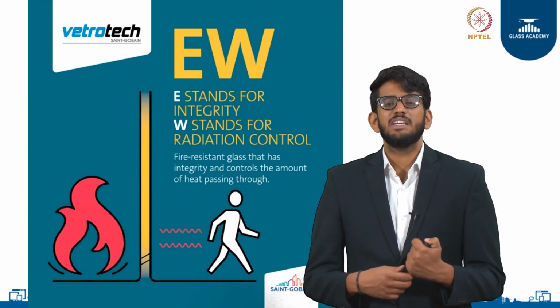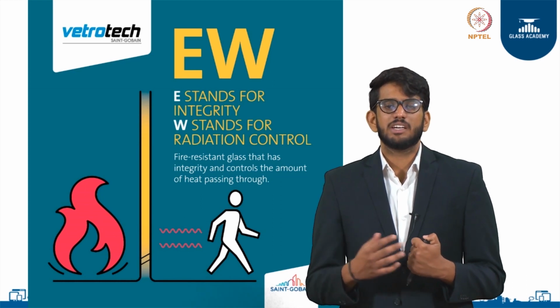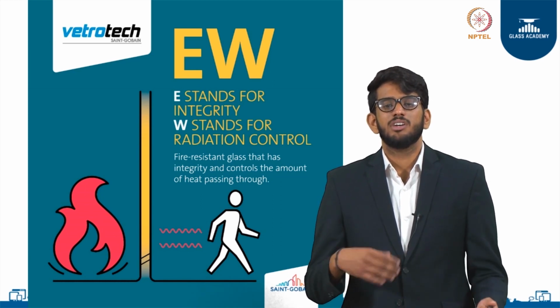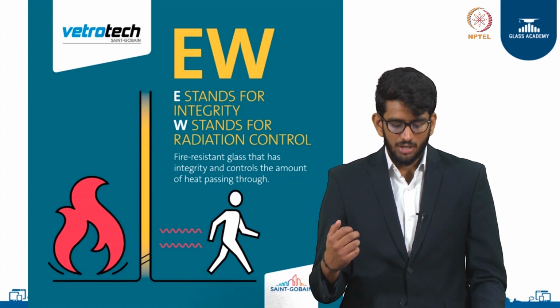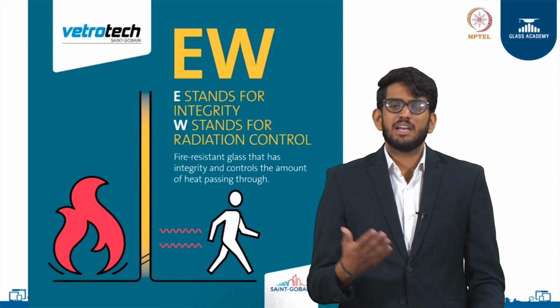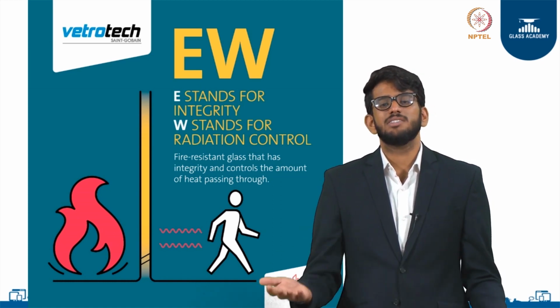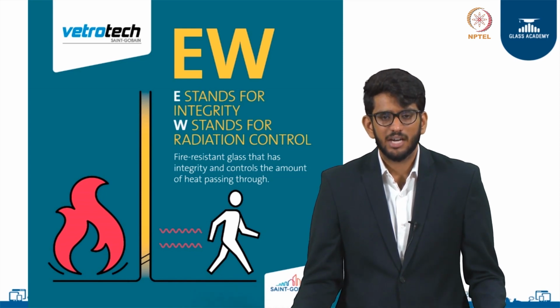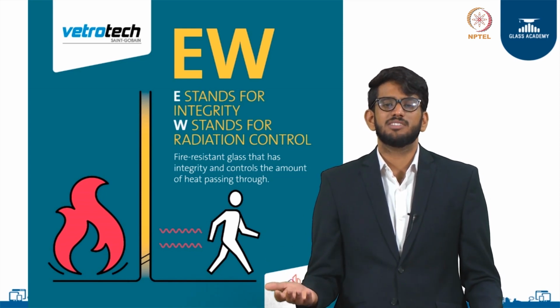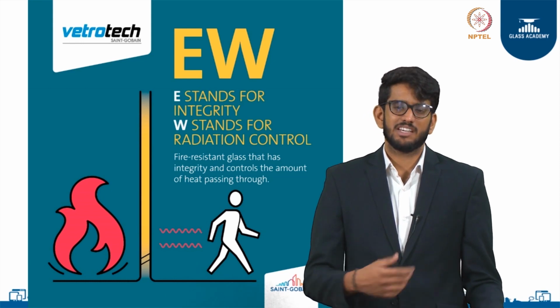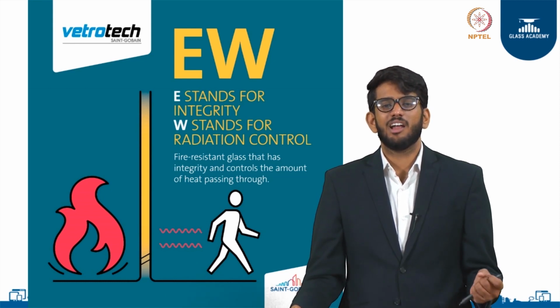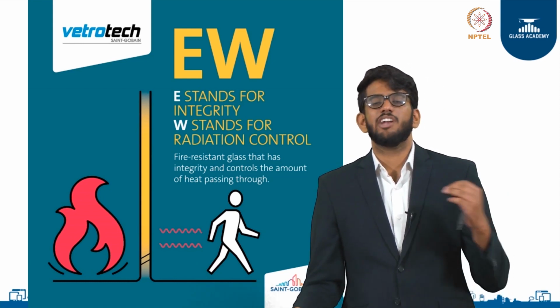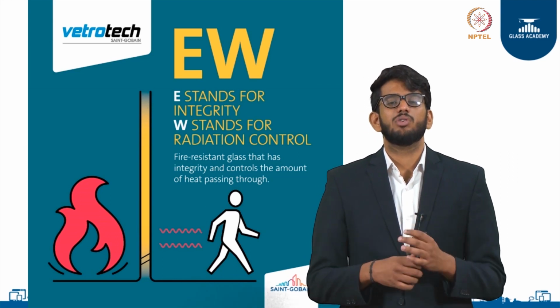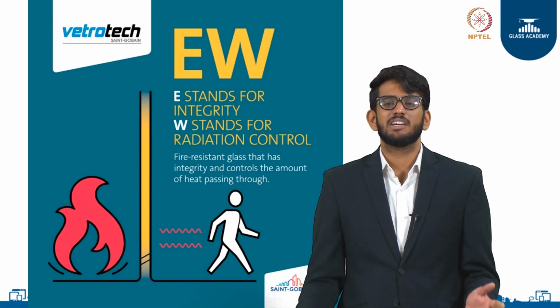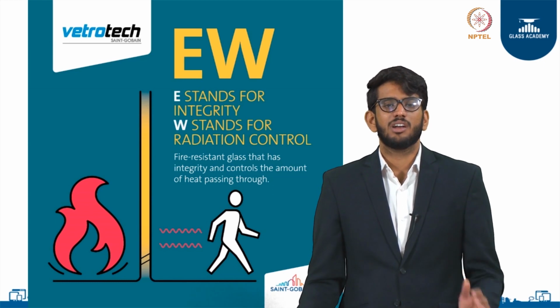So, again, the E in the EW stands for integrity and the W stands for radiation control. An E-rated glass is a more basic type of classification when you compare it against an EW-rated glass, because an E-rated glass does not cut down the amount of radiation coming through the glass, but it does provide integrity and structural rigidity to the glass barrier.